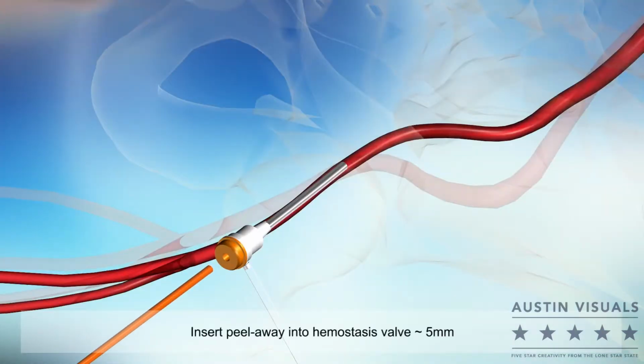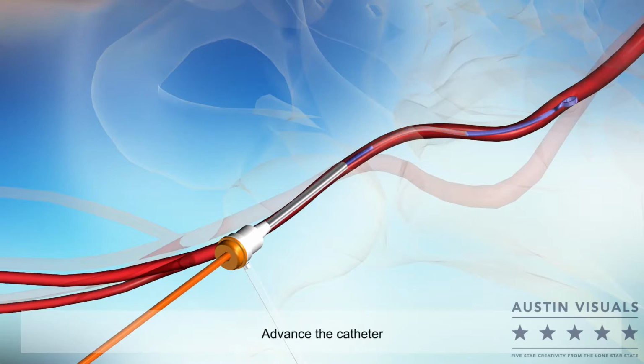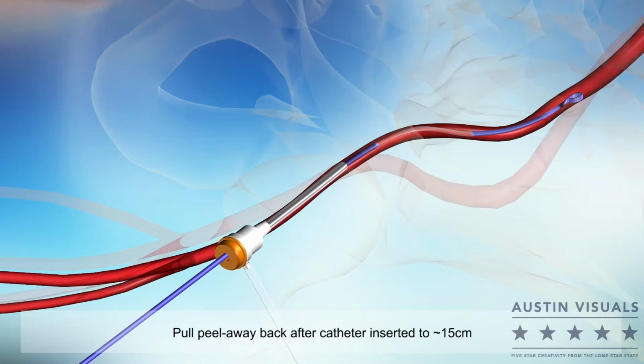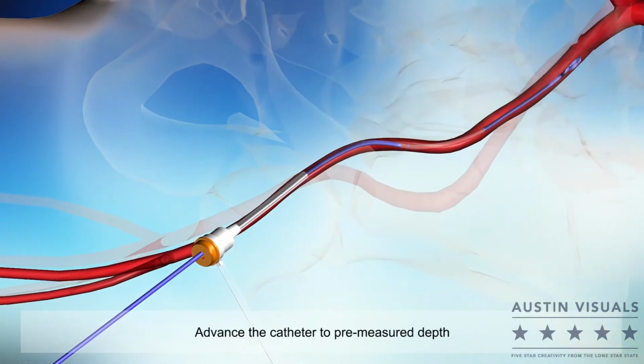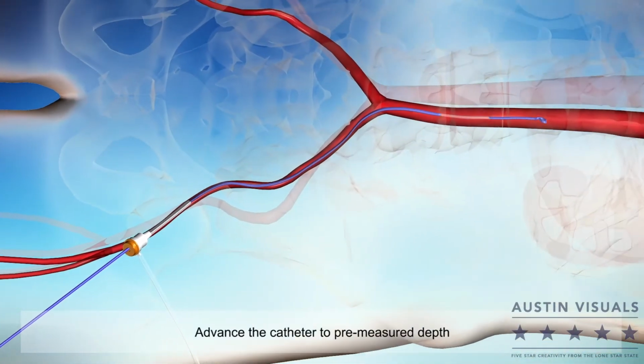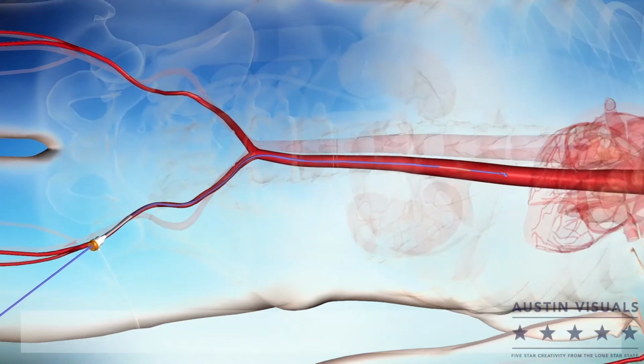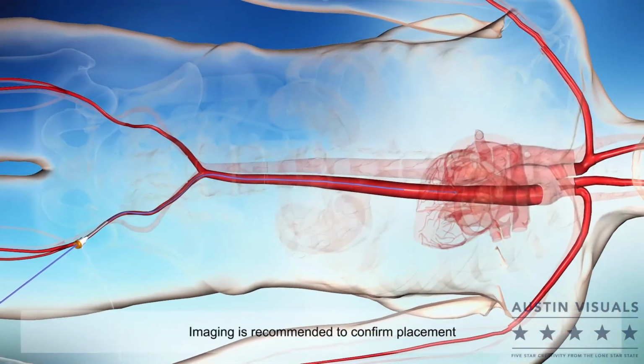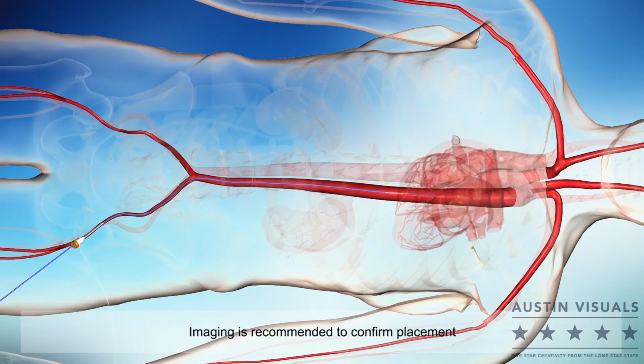Insert the peel-away into the 7 French introducer and advance the catheter approximately 15 centimeters, then slide the peel-away back on the catheter shaft. Continue to advance the catheter into the appropriate zone at the pre-measured depth. If available, use of imaging is recommended to confirm placement.